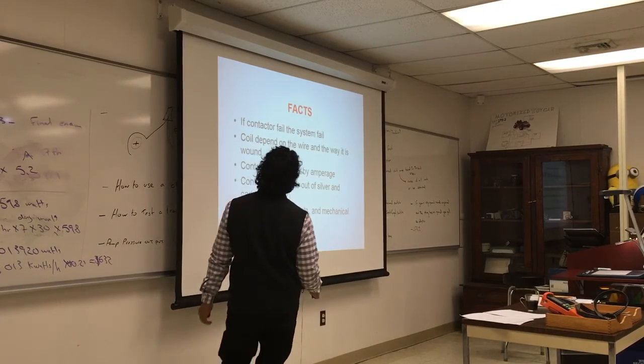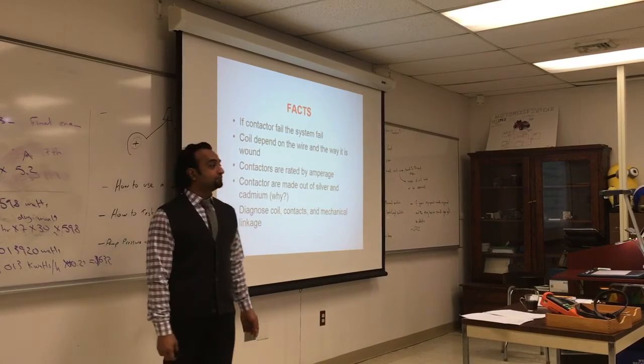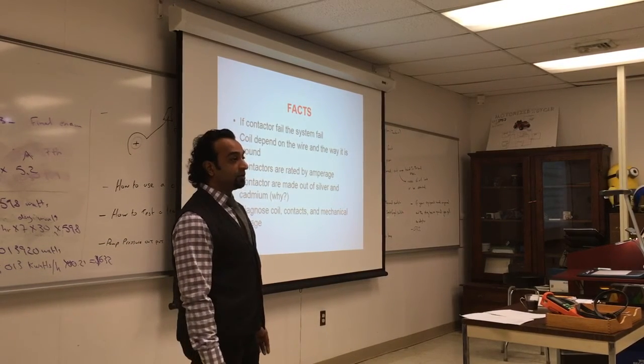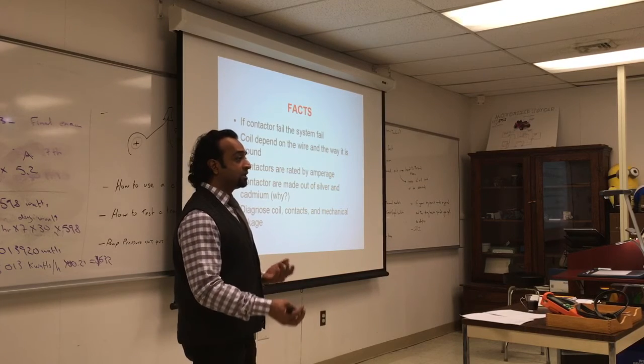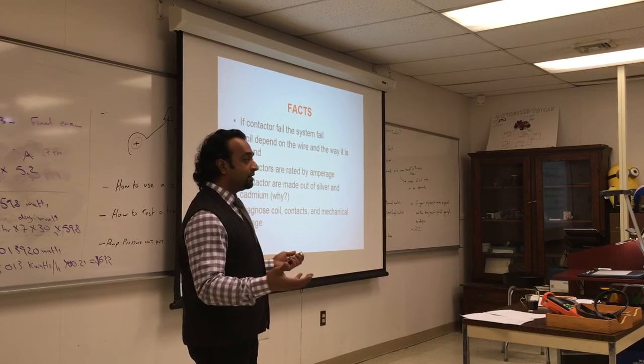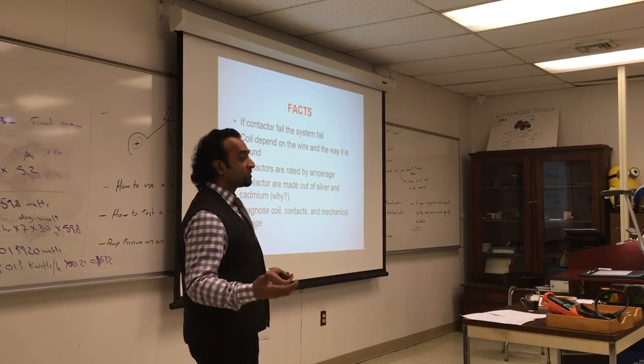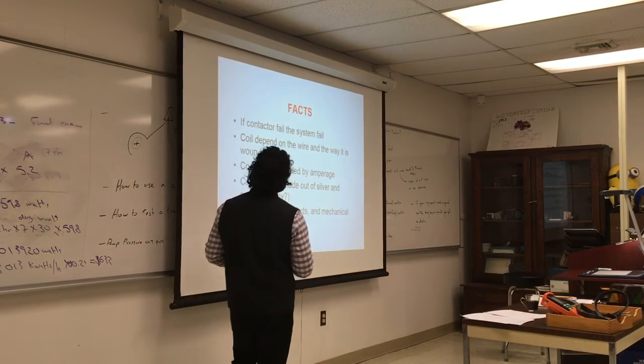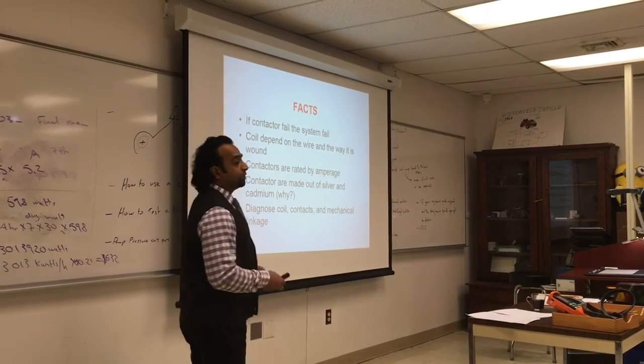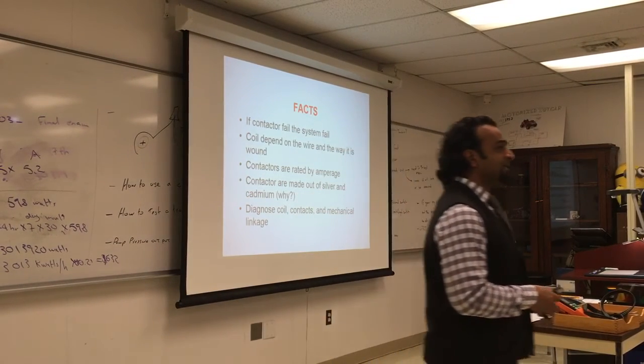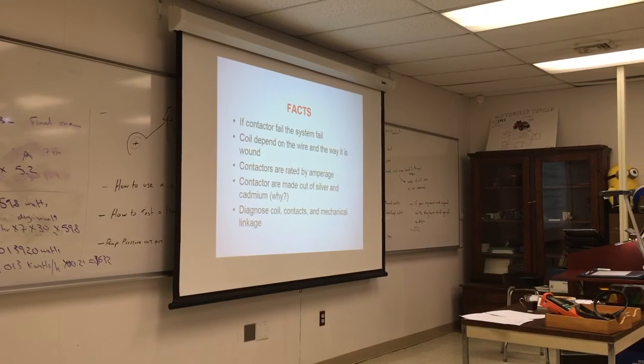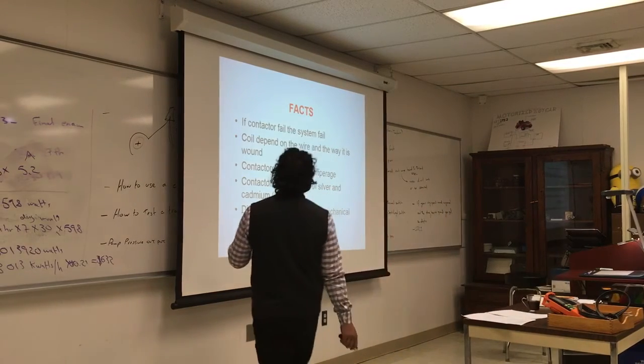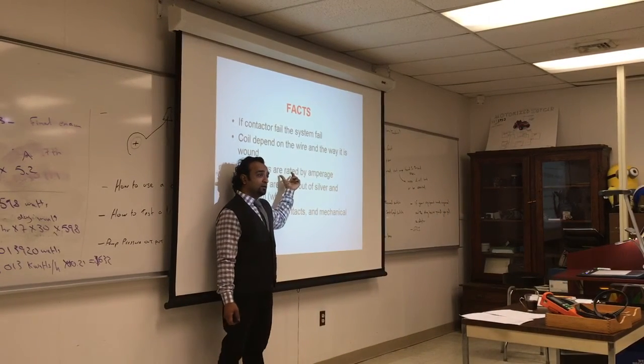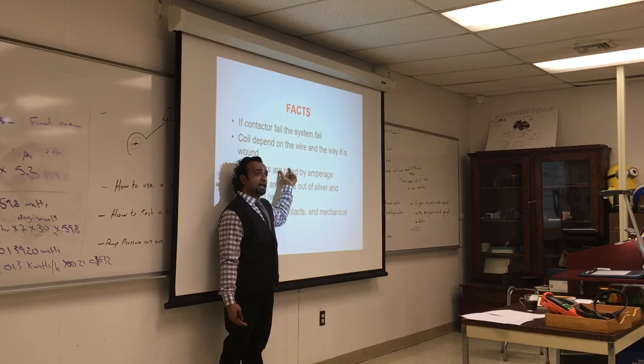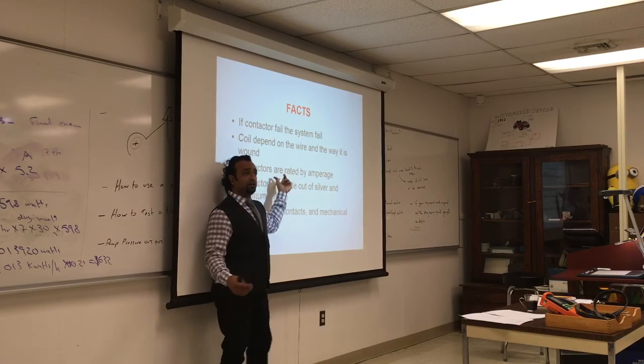So facts, if the contactor failed, the whole system failed. Yeah, because you've got to treat it as a unit, right? Yeah, and also because the whole logic and system of operation of the whole equipment is gone. So you have to change it, the contactor is very important. The coil depends on the wire and the way it is wound. So what does that mean? The coil strength as a magnet depends on how thick the wire is and how it's wound to make that magnet. Contacts are rated by amperage, we learned that, right? Yes. What is the difference between a contactor and a relay? The amperage. So contactors and relays are rated based on the amperage.